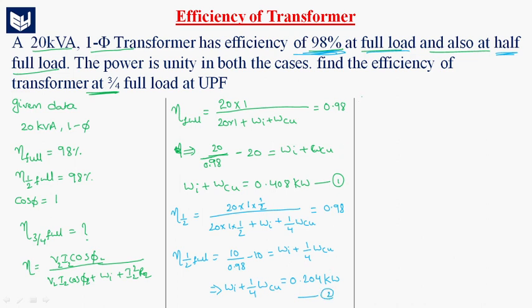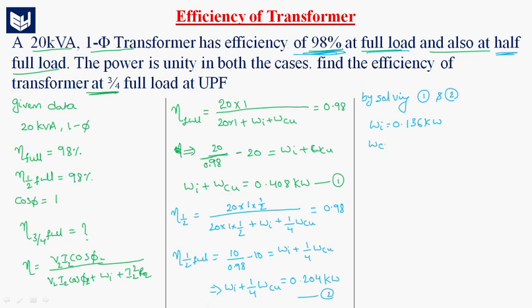Now, by solving equations 1 and 2: Wi plus WCU equals 0.408 kilowatts, and Wi plus 1 by 4 WCU equals 0.204 kilowatts. We get iron losses Wi equal to 0.136 kilowatts, and copper losses WCU equal to 0.272 kilowatts.